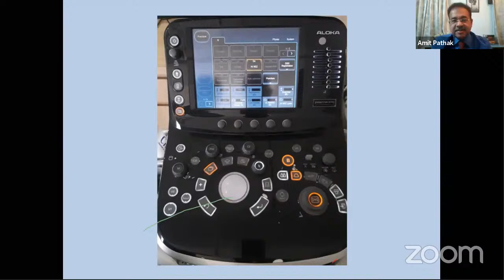Now, this is a TGC curve, and there's something very simple about it. You can imagine that an ultrasound goes into the tissue from the surface. So that is the upper part, where it enters. It penetrates down to the lowest part and comes back. All the ultrasound which enters just from the surface and comes back, because from every point within the organ ultrasound is being reflected back, is nearly all reflected back, because it did not have to penetrate and lose its energy while going through the organ. Whereas deep, where deep is written, at the lowermost part of the ultrasound beam, when it is penetrating, a lot of its energy is lost because it has passed through the tissue all this distance.